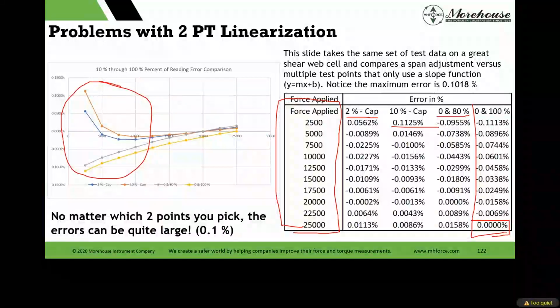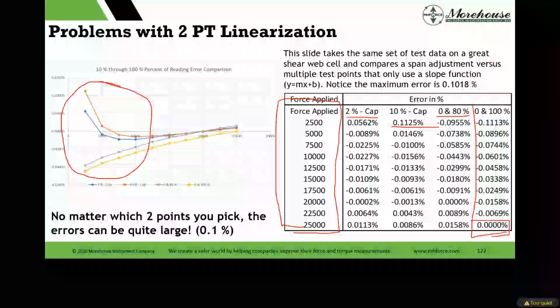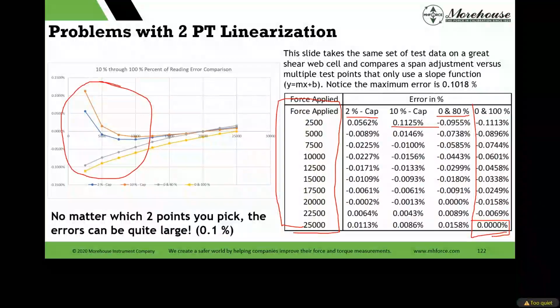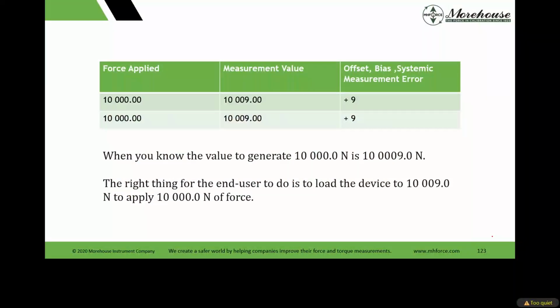These numbers are the percentage off from nominal force. So this might help when I talk about that. That means my force applied is something, and my measured value may be off. That's what I call a bias, offset, systemic measurement error. All these terms, the vocabulary international metrology defines some of them. I like to say it's just a bias, right? We know if it's repeatable, it's a bias, and the bias should be corrected for. A lot of people do not do that, but that's another story.